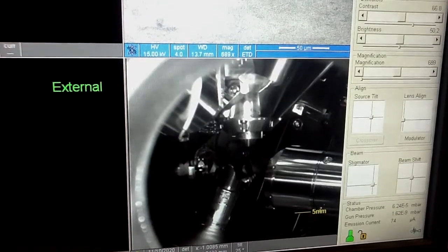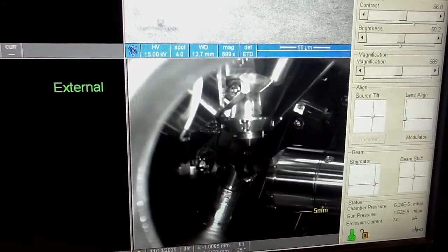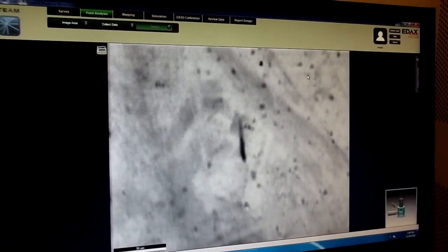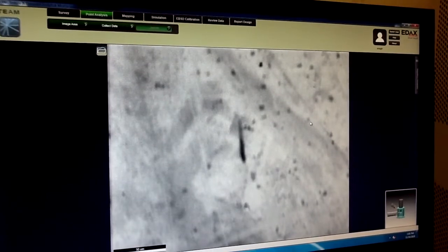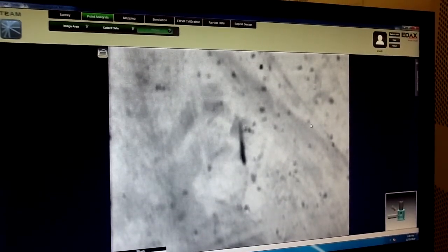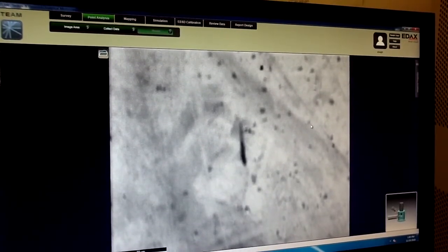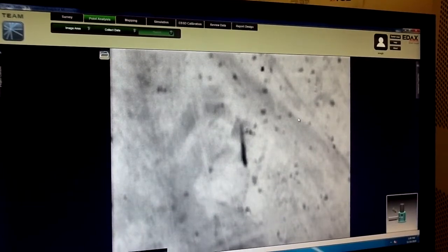If it is too big, there is a good chance that the detector will hit the stage or your sample itself. Once the detector has been completely inserted, you will see an image of your sample. The image might appear to be different from what it is on the SEM screen. This software corrects the image for the angle of inclination of the sample.